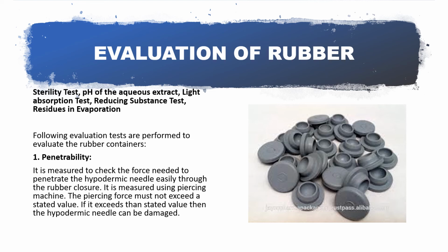The first is the penetrability. It is measured to check the force which is needed to penetrate the hypodermic needles easily through the rubber closure. So it is measured using a piercing machine. The piercing force must not exceed a stated value. If it exceeds that stated value, then the hypodermic needles can be damaged.